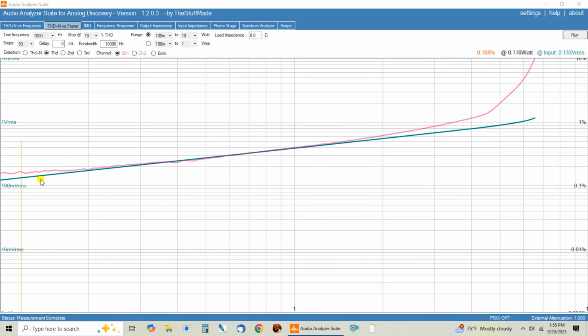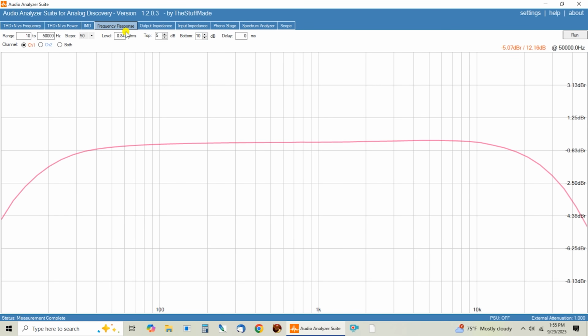So again, this is the THD versus power. Okay? So then we're going to come over here and look at the frequency response. So here I looked at what's the input voltage at 4.5 watts. Because we want to do all this testing near the max power to really stress the output transformer. And I think that's the point we're going to see the differences in these transformers. So we got 0.84 volts RMS in, gives us 4.5 watts. So we did our frequency response at this same 0.84 volts RMS in.